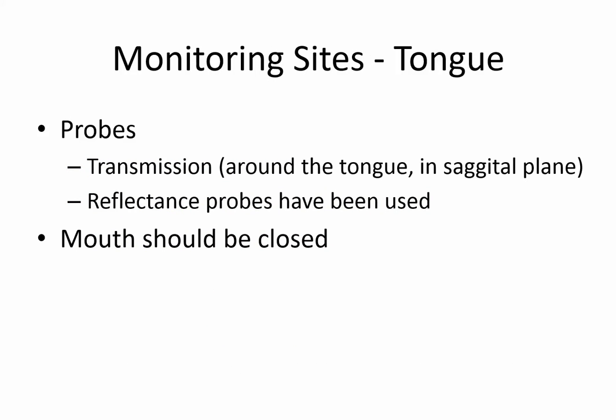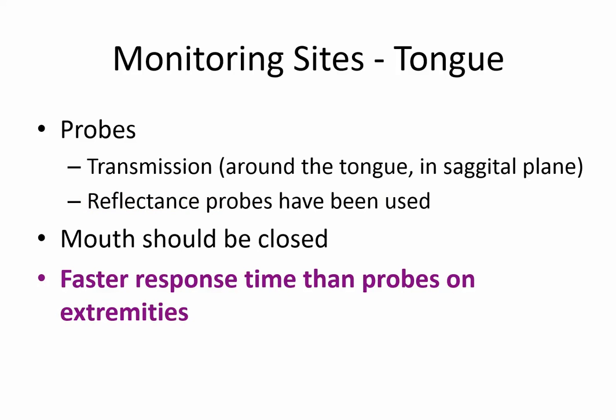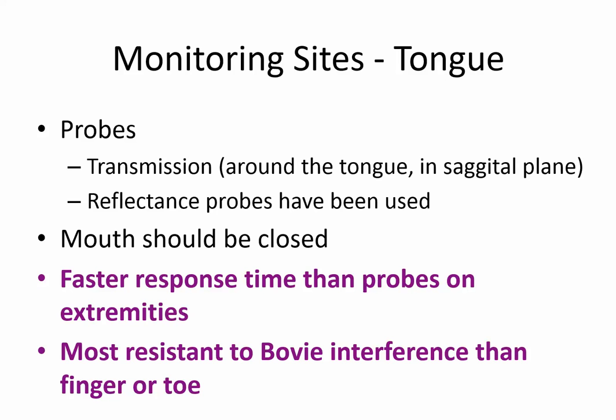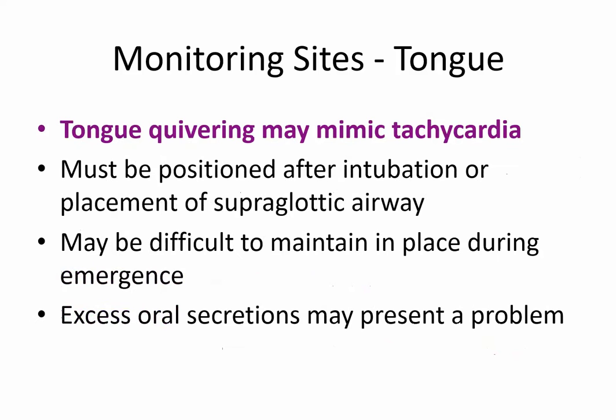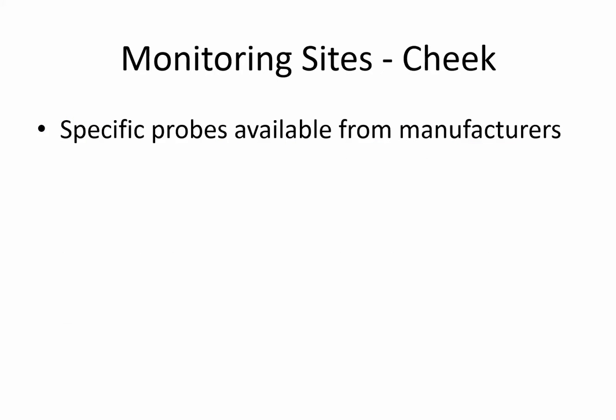The tongue. It's primarily a transmission probe, as you wrap it around the tongue in the sagittal plane, although some reflectance probes have been used, and they suffer from the same limitations as all reflectance probes. The mouth should be closed. It's got a faster response time than on the extremities. It's more resistant to Bovie interference than the finger or toe. But tongue quivering may mimic tachycardia. It should be positioned after intubation so you don't dislodge it. It may be difficult to maintain in place during emergence, and excess oral secretions may present a problem.